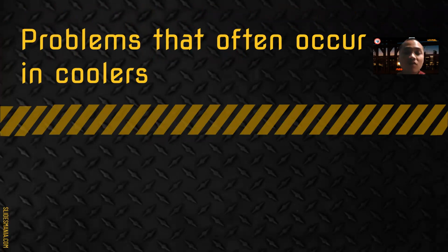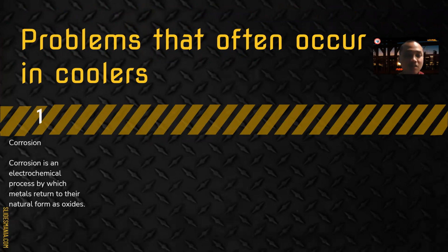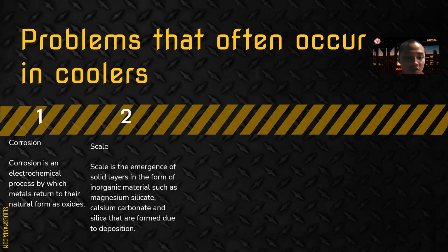Problems that often occur in coolers. Number one is corrosion. Corrosion is an electrochemical process by which metals return to their natural form as oxides. Number two, scale. Scale is the emergence of solid layers in the form of inorganic materials such as magnesium silicate, calcium carbonate, and silica that are formed due to deposition.